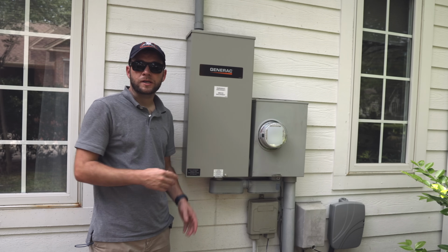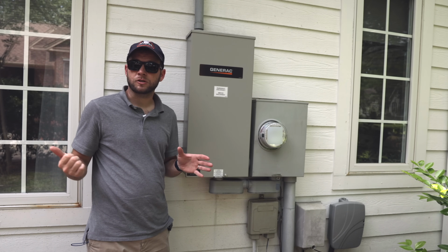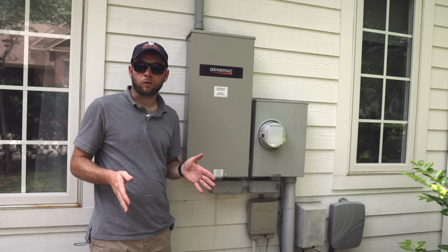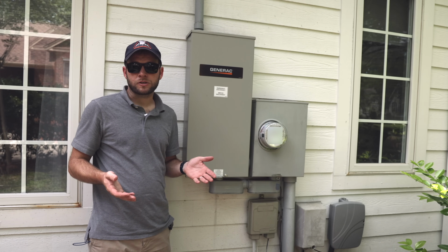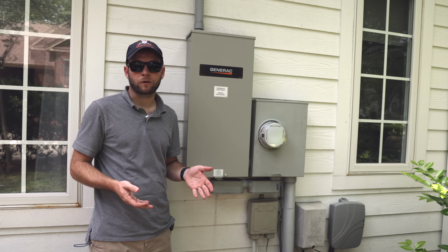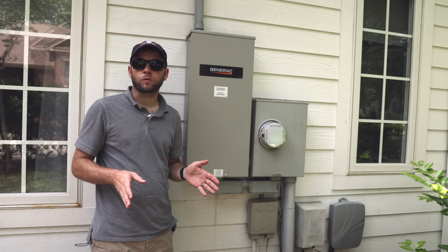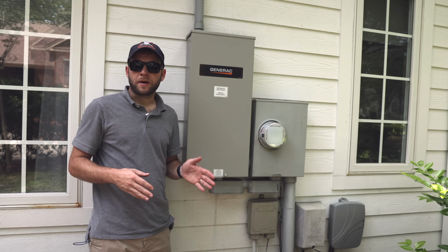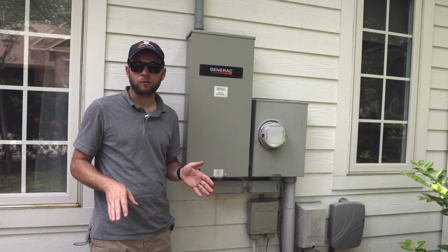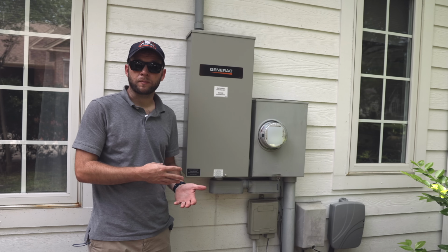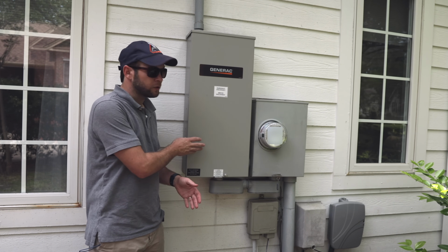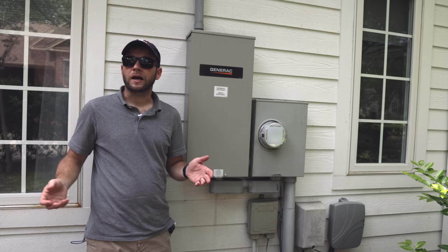What that's going to do is power is going to constantly be sent to the generator that we looked at that is sitting there waiting for the power to go out. This is going to allow it to use its power, keep running, keep a trickle charge on its starter battery, and make sure that everything is running properly.